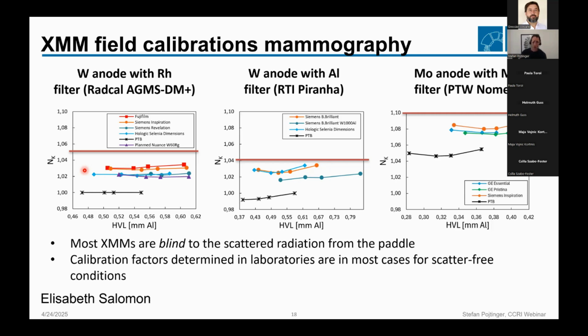What I also wanted to mention is that some manufacturers, for example, RTI Piranha, in their manual, you will find a correction for that. They will tell you if you want to compare to an ionization chamber and you need to include scatter, you can just multiply by a factor of, I'm not 100% sure, I think it's around 6%. So this is a tabulated value for that specific device.